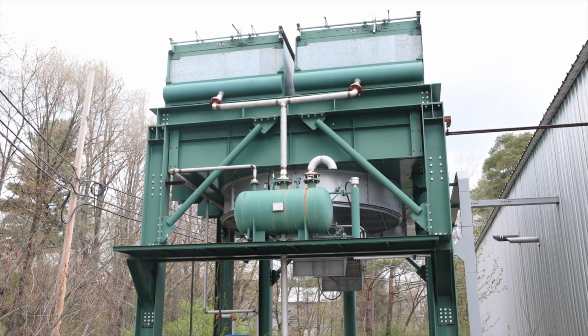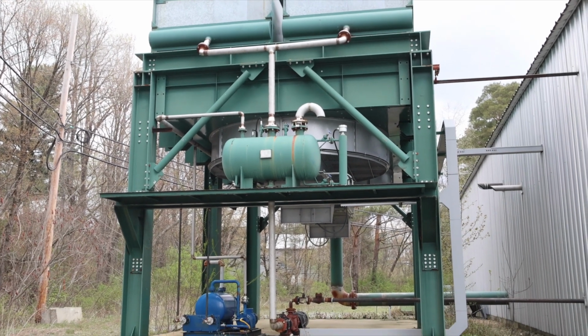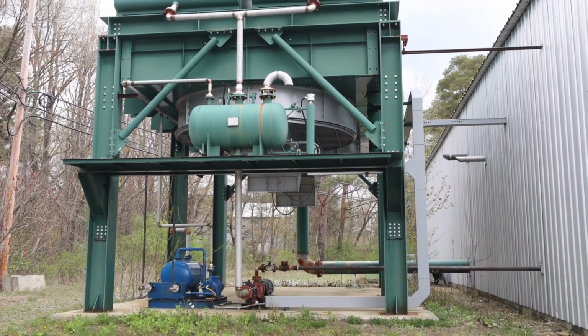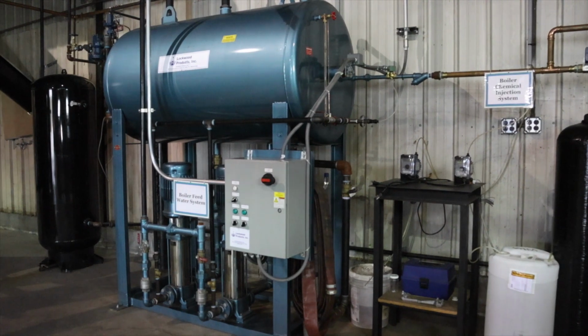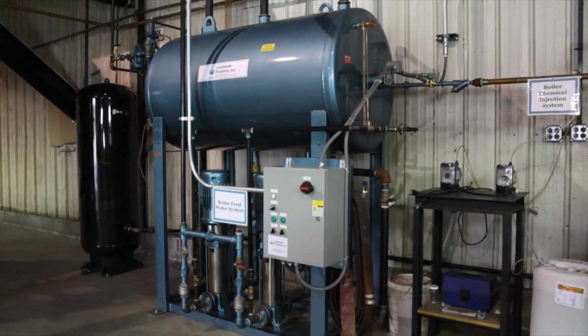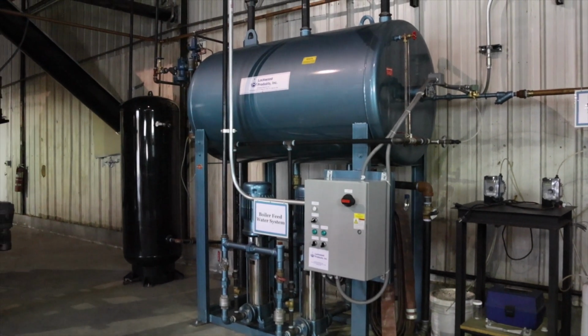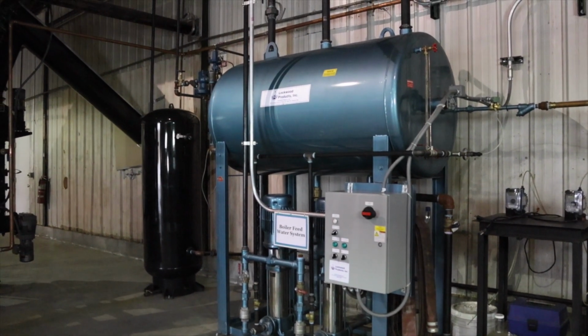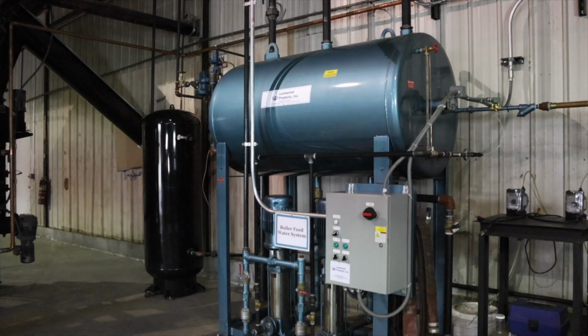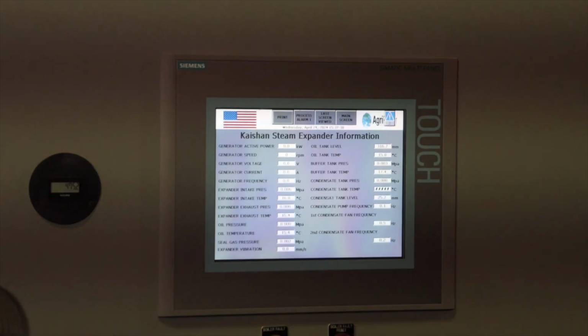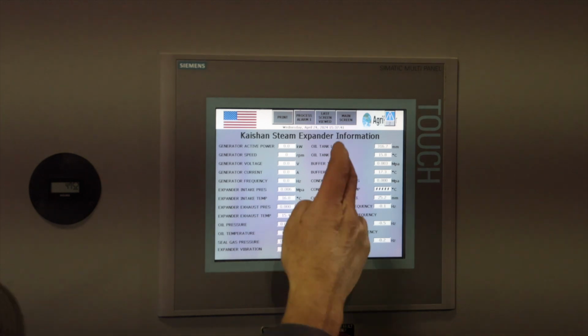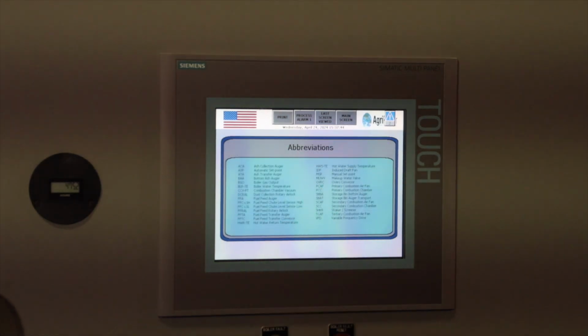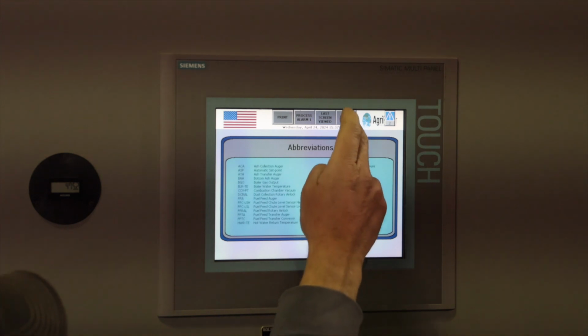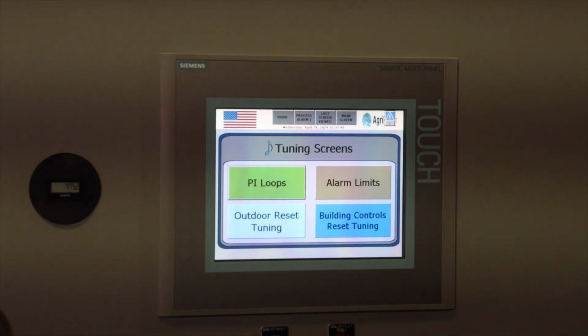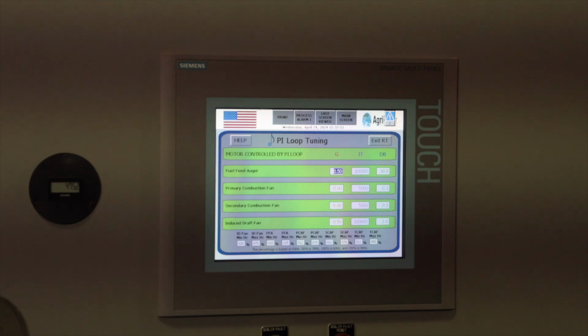The condensate water is then pumped back to the boiler feed water tank by the condensate pump. As the boiler feed water system receives the condensate water from the condensate pump, the closed loop is complete and the water is once again fed into the boiler on demand as boiler feed water. The screw expander skid and related equipment are also monitored and controlled by an HMI touchscreen. As with the combustion system, all information and control parameters are controlled and displayed on various screens for operator interface.